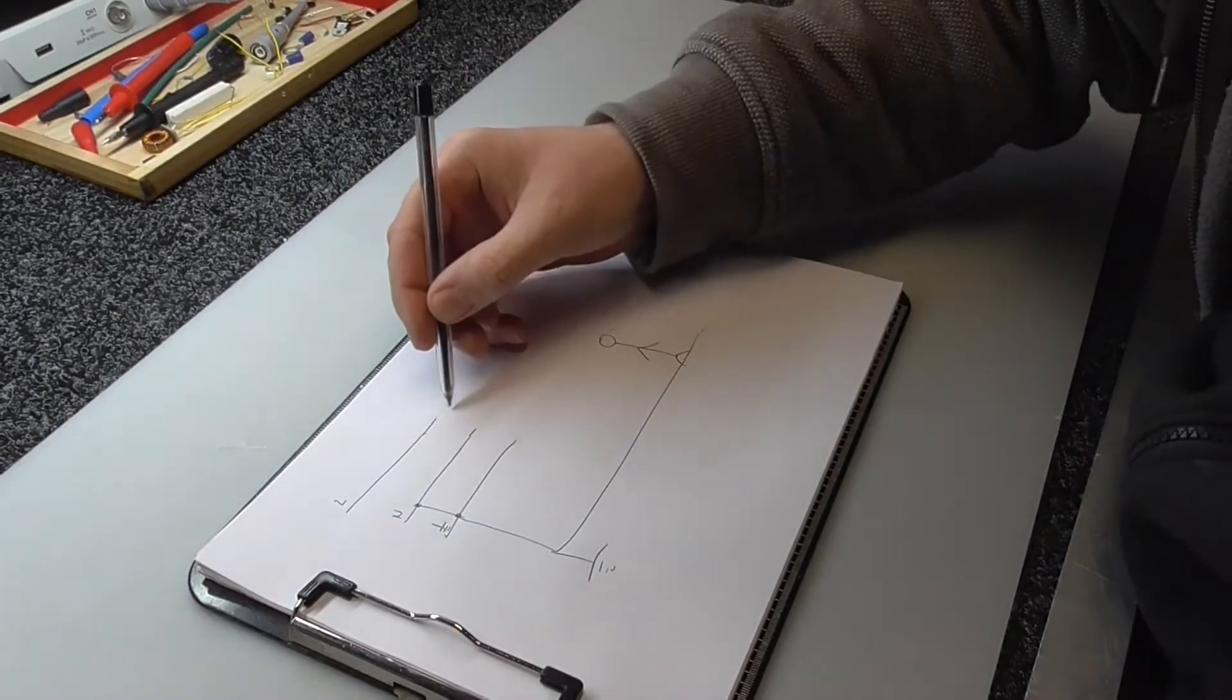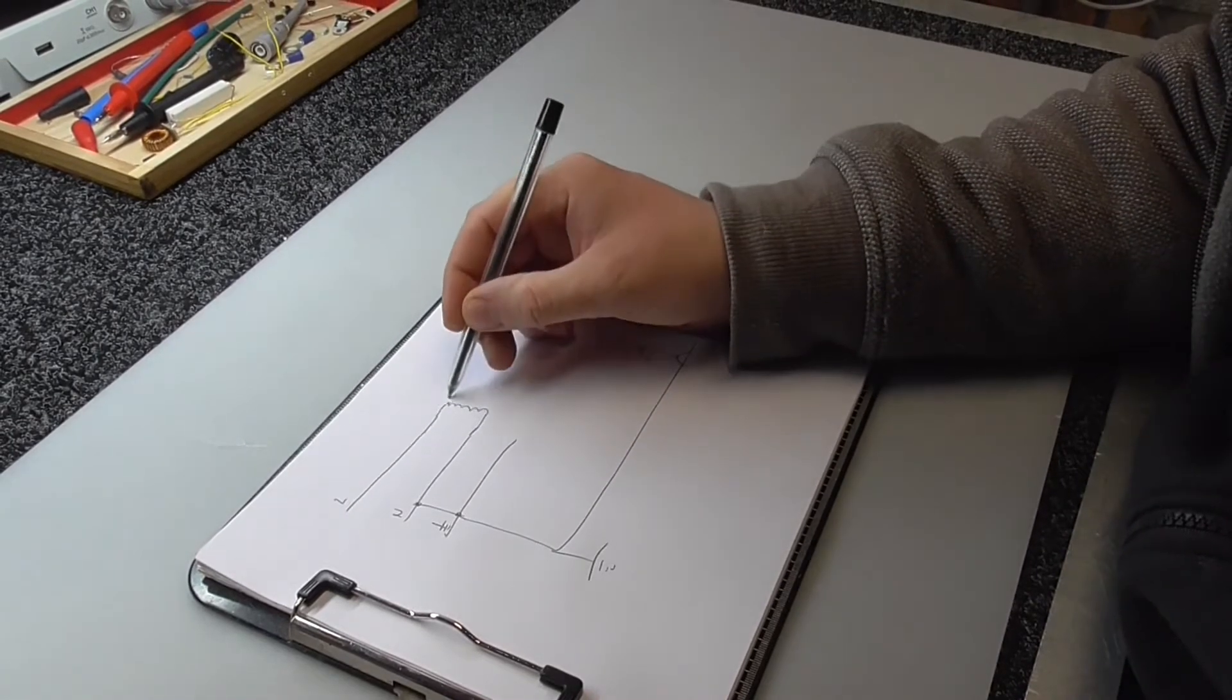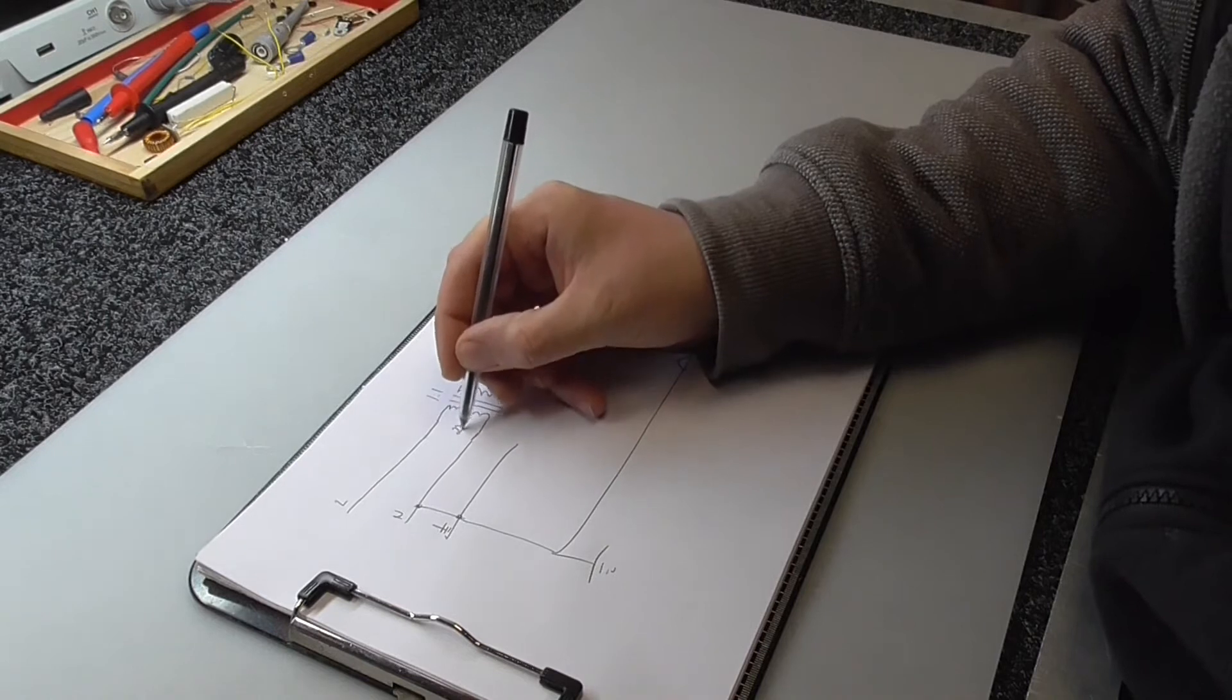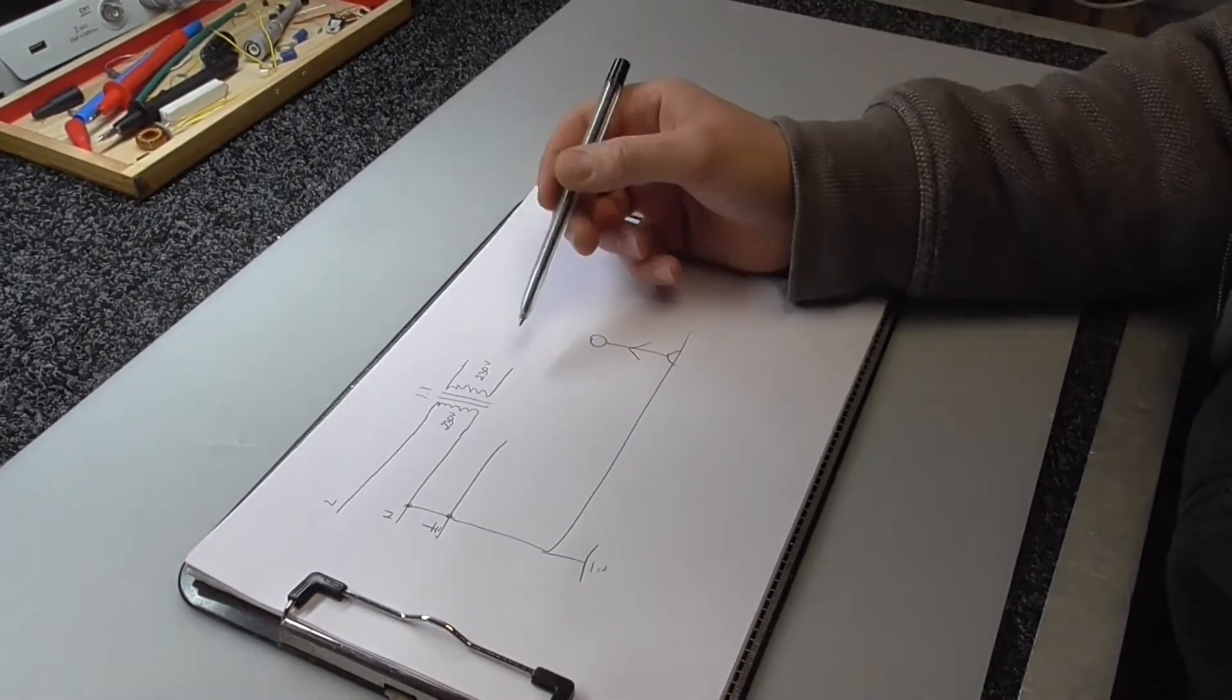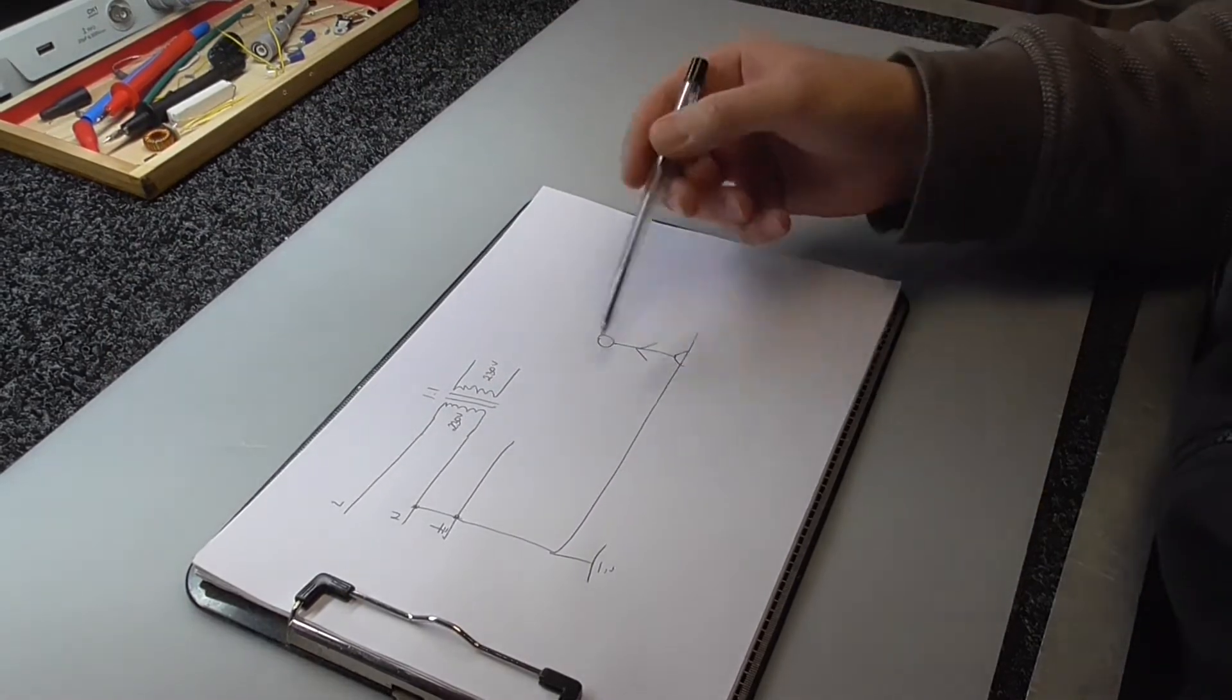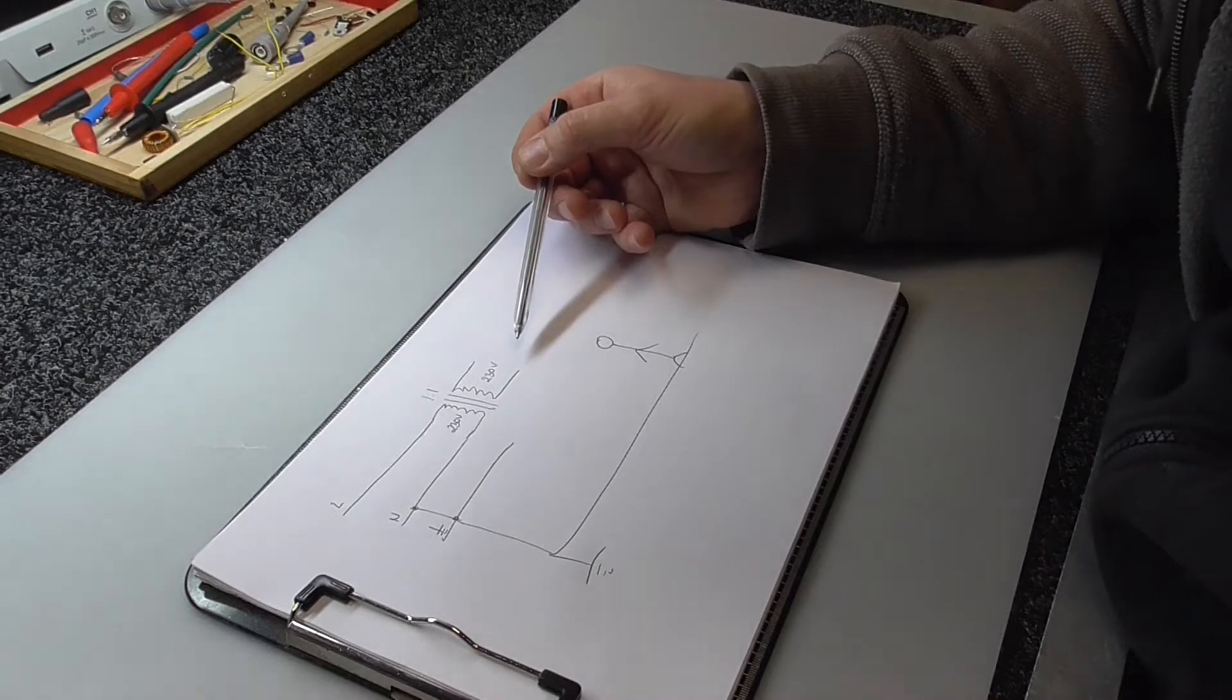The idea of the isolating transformer is to put a transformer in with a ratio of one to one, so we will have 230 volts on the primary side and 230 volts on the secondary side. But we are actually isolated by this transformer from the mains. So we are still grounded, but we are not one of the potentials for this voltage on the secondary side. If we touch one of the wires, we will not get electric shock.